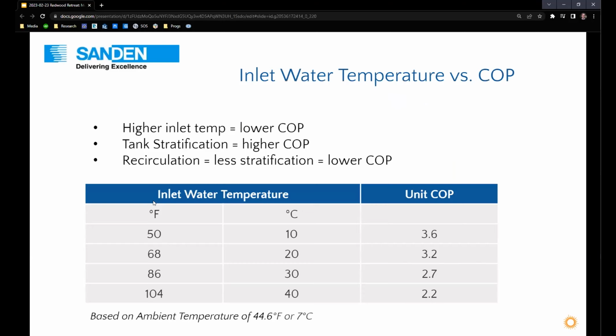We learned some lessons on those initial installs as well, where we struggled with recirculation. I think it laid some of the foundation for swing tanks as the preferred strategy, or really the isolation of recirculation. When you're doing a heat pump water heater system, you really need to isolate recirculation from the heat pumps, particularly a single pass heat pump like a Sanden, because the Sanden is really happy and has a high COP and also its highest output when you're giving it 60-degree, 50-degree inlet water, which is the temperature of incoming cold water. And it likes to heat that up in a single pass to 150 degrees.